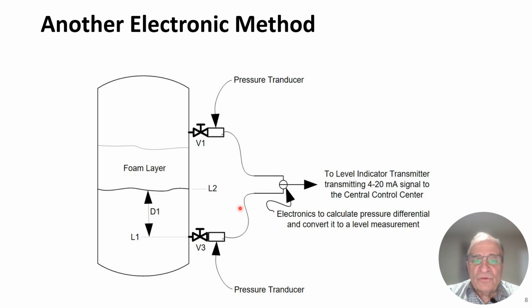Because let's say this was broken and you ended up with a 0 reading, you might think you're at 0 level when in fact you could be at some high level. So a 0 level or 0 milliampere signal will tell you that there's a fault. Something is wrong with the system because it's not showing any signal at all. So it could be a break in your wiring. It could be a bad connection or something else. But the 4 represents 0 level.